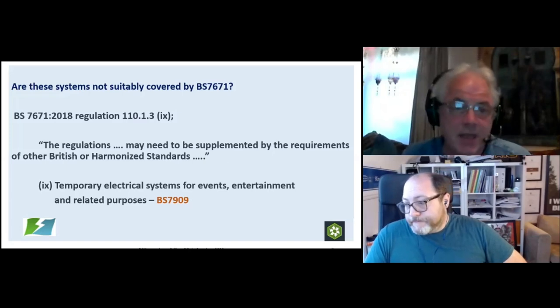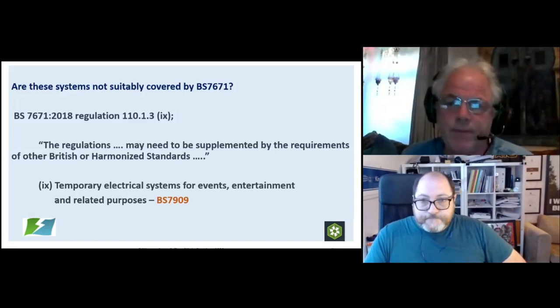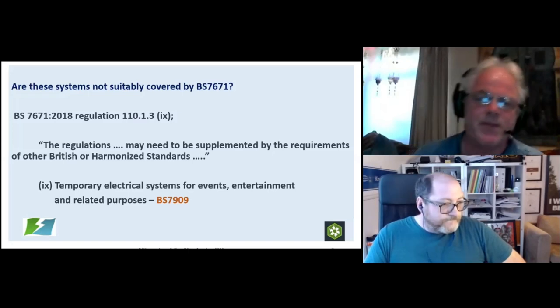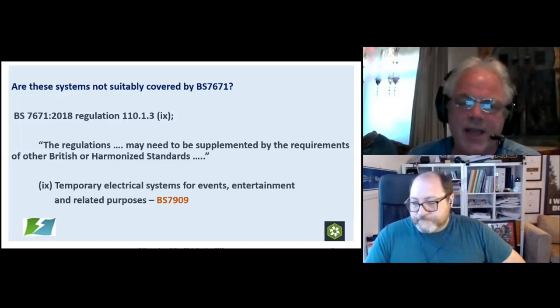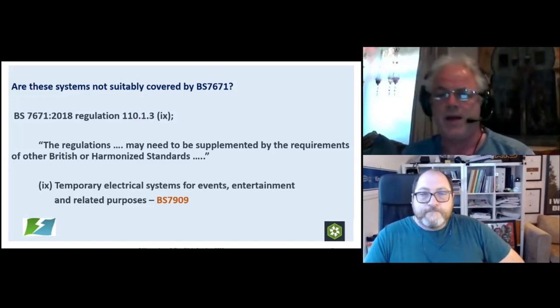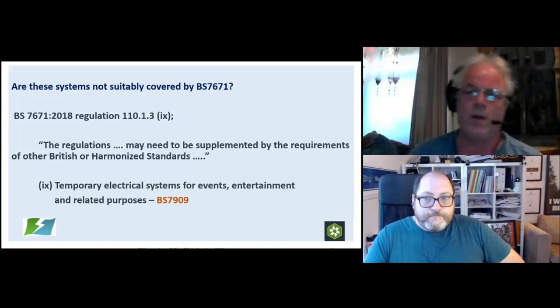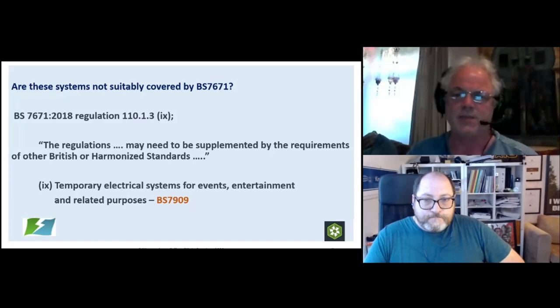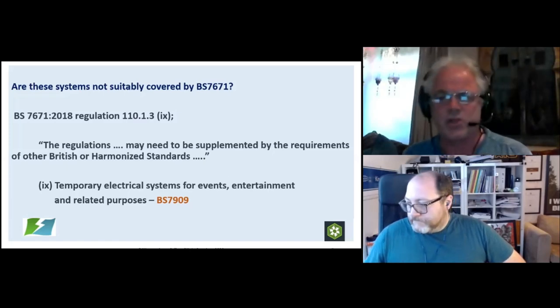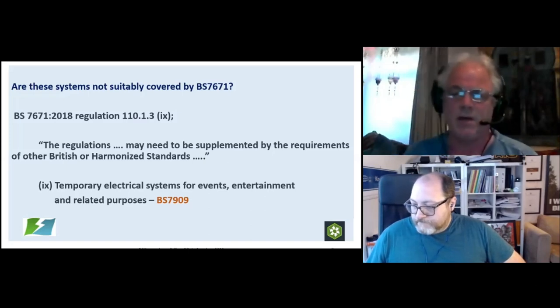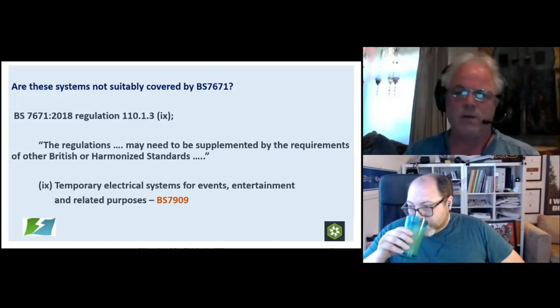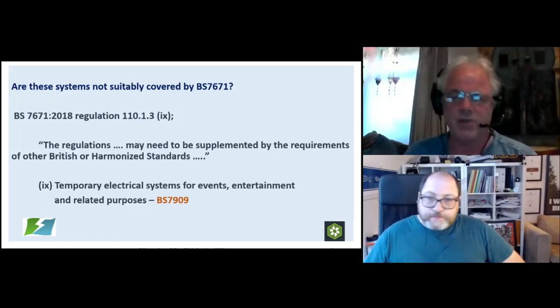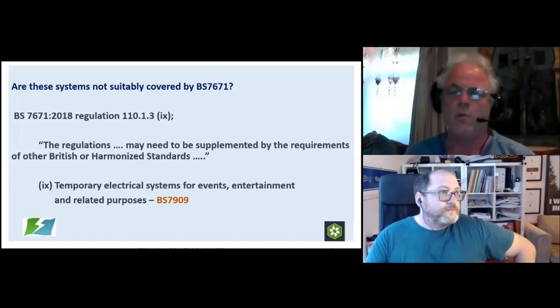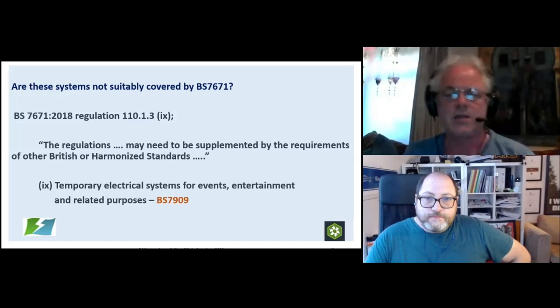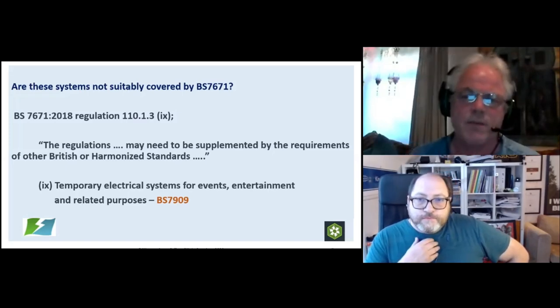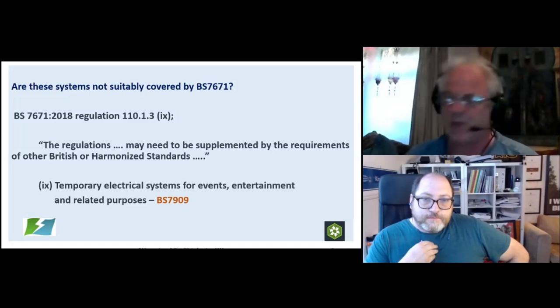As it states in BS7671, in part one, the regulations may need to be supplemented by the requirements of other British or harmonised standards. We talk about fire alarm systems, we talk about emergency lighting, BS5266. We cover emergency lighting to an extent in BS7671, where we're looking at the type of cabling, the type of protection and everything else. But what BS7671 doesn't tell you for emergency lighting is your lumen requirement, where to actually put these things, the location, and the inspection and testing regime for emergency lighting. All of that is in BS5266. So for temporary events, we have this additional document, this code of practice, BS7909, to cover all the temporary electrical systems.